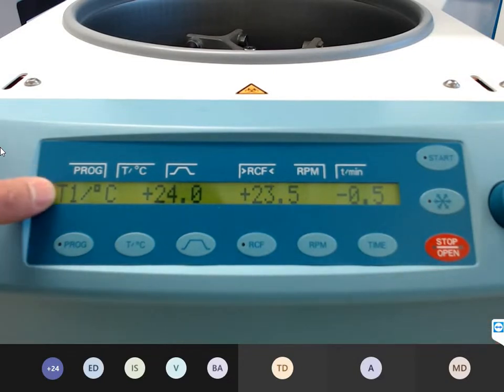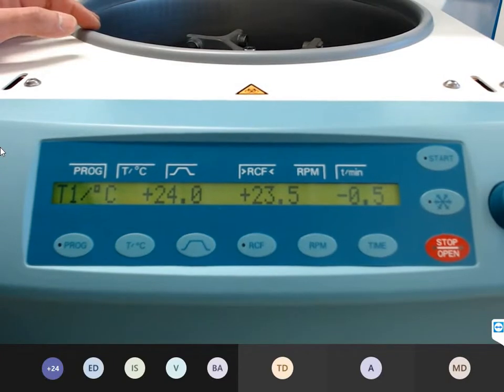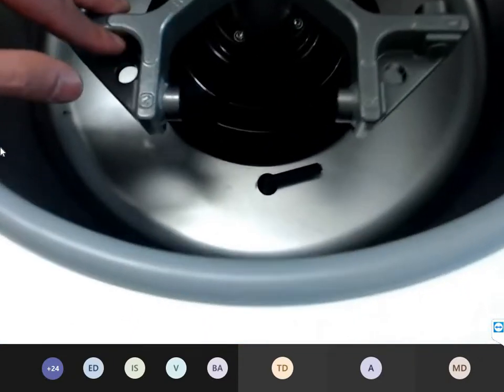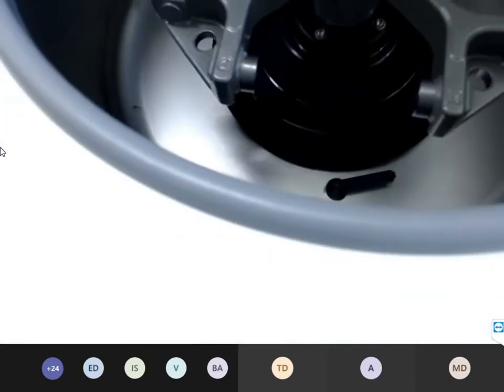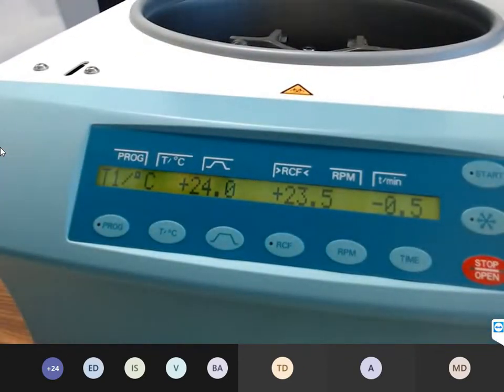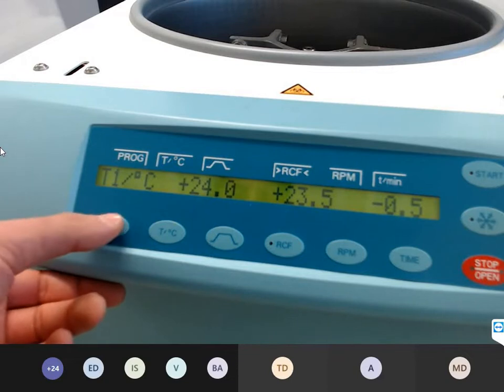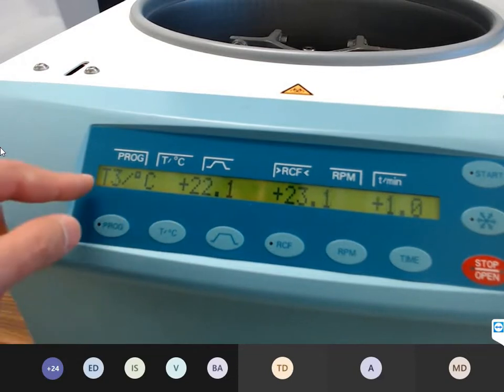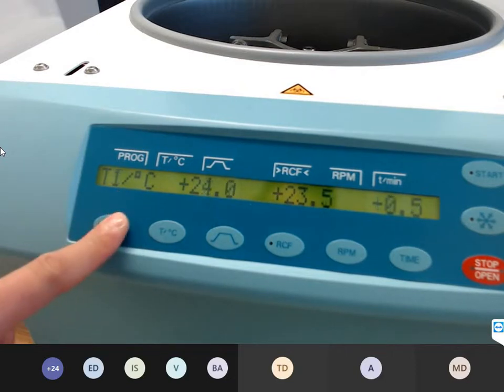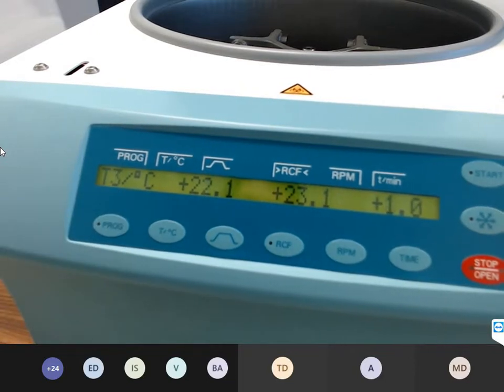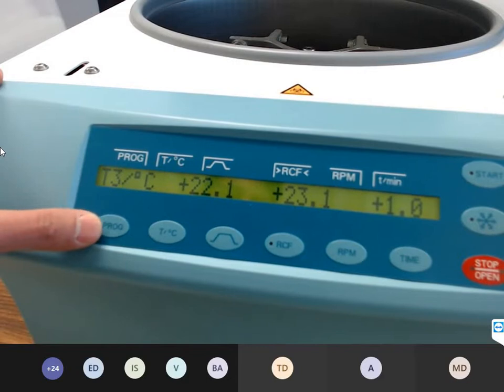We have here 3 temperature sensors. T1 means the temperature sensor in the chamber, the black one. If you change this sensor, please make an offset adjustment. T3 is on the condenser. Yes, only these 2 temperature sensors.